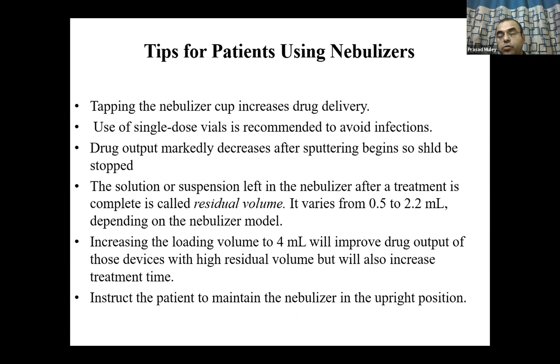Use of single dose vials is recommended to avoid infection. Sometimes the solution is available as 5 ml or 10 ml, but rather than using that, respules are preferred because they avoid infection. Drug output markedly decreases after spluttering begins, so the treatment should be stopped. Solution or suspension left in the nebulizer after treatment is complete is called the residual volume. It varies from 0.5 to 2.2 ml depending upon the model of the nebulizer. Increasing the loading volume will improve the drug output, but devices with higher residual volume will also increase the treatment time. Instruct the patient to maintain the nebulizer in an upright position, as it helps in proper drug delivery.